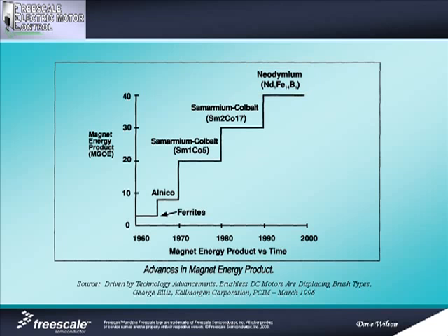You really have to be careful when you're working with NEO magnets. In fact, these magnets are so strong that something as simple as manually inserting a rotor with NEO magnets on it inside of a motor frame can be very dangerous. It turns out that the attraction force increases dramatically as these two pieces come closer together. And some customers have even reported incidents of personal injury as the rotor gets sucked inside of the stator frame.